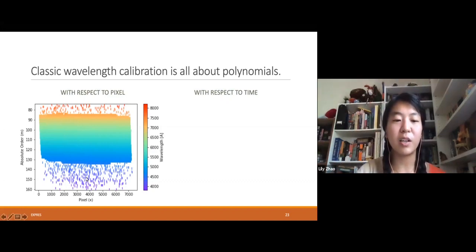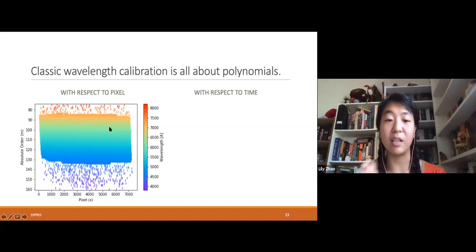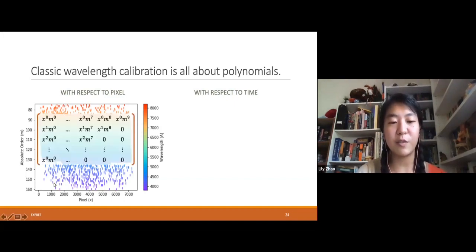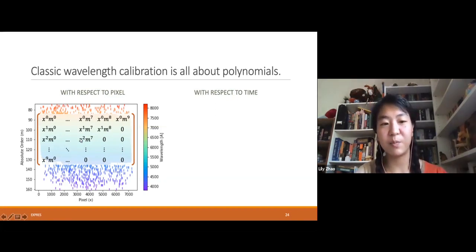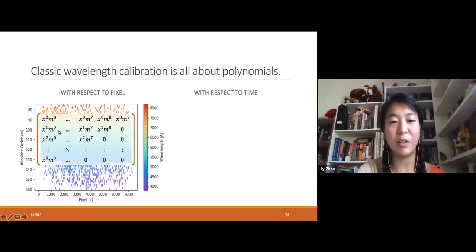And so this is plotting all of the calibration lines we have for which we know the wavelength, which is the color. The sparser areas are the thorium-argon lines, and this is the area where we have that very densely sampled LFC information. And so classically, what you would do is fit a 2D polynomial to this information with respect to detector position and order, where y is the wavelength. And so you'd fit a 2D polynomial to interpolate what the wavelength should be with respect to pixel.